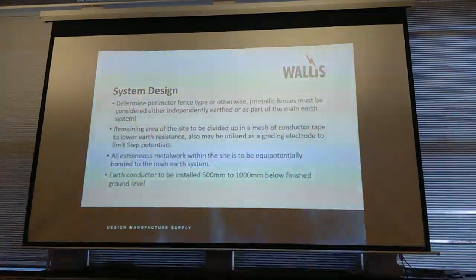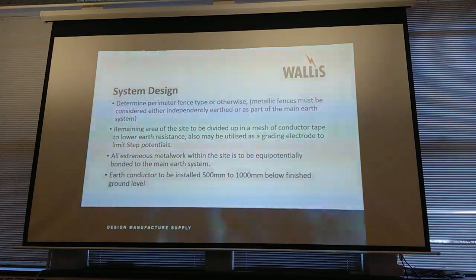So if you've designed something based on 100 ohm meters resistivity, and you know the fault levels and the resistance is fine at that, and then the ground freezes, your earth system has actually lost all its performance. The actual resistance to earth then could go up quite dramatically. So your rise of earth potential could go up, your touch potentials could go up, your step potentials go up, and you could end up with an unsafe site just because the ground's frozen. So that's something else you've got to be a bit careful of.